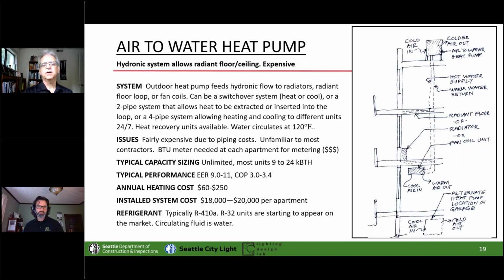So having a hydronic system through your building is great. As you see there, you could have a heat pump on the roof or elsewhere. Like you see at the bottom of the diagram, you could have the heat pump down in the garage where temperature stays a little more cozy. And then that can feed a radiant floor system, or a typical radiator at the window, or fan coil. There's a number of alternatives that you can do with that heat. You could do a 2-pipe, which would mean in most cases, you've got to switch over seasonally from when you end your heating to when you start your cooling.